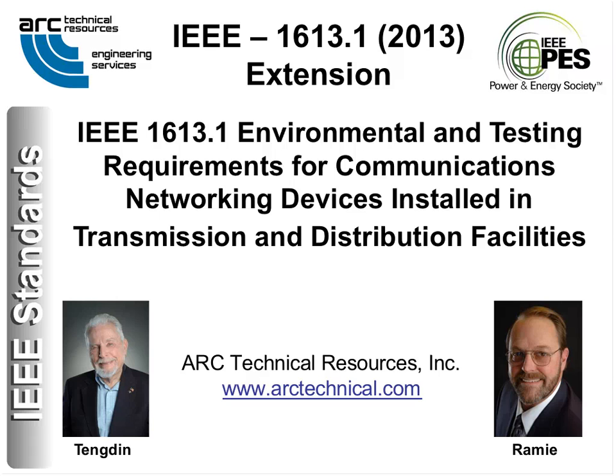Okay. Next question from Ravi Sitapati says, most relay racks in extra high voltage and high voltage substations do not have doors. They're just open racks. So what do we do now? You buy products that are tested to the IEEE 1613 and 1613.1 pair, because the cabinet has to live in its intended environment, and for you that's an open rack. Tell that manufacturer that you run in open racks and that he'll have to pass in an open rack. Remember, that comment about closing the doors was informative. It's not part of the document. It's just a story that we tell inside the document.